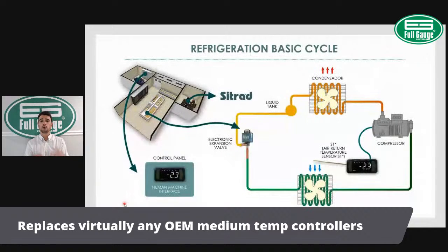So on the basic refrigeration cycle, on a medium temp application, the controller will be either connected to the compressor or the solenoid valve. In that case, the evaporator fan will be connected either direct into the line so that the evaporator fan runs continuously, or we're gonna connect the evaporator fan together with the compressor. So the fan cycles on and off together with the compressor. Let us look now how to wire the controller direct to the compressor in that case. Again, in this application, the controller is basically controlling the compressor, and you have a temperature sensor on the air return. So based on the air return temperature, you have the compressor on and off. How do you connect to the compressor? That's what we're gonna look at in here.